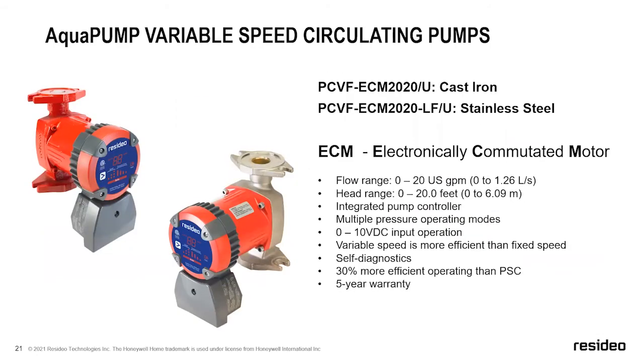And I did want to touch on our variable speed pumps. So we have finally entered the realm of variable speed pumps. We have had 3-speed fixed circulators for a while. We are now finally producing an ECM variable speed pump. So we are offering our same curve on our lower circulator, but we're offering it in 2 different configurations. So we got cast iron and stainless steel. And as I had mentioned previously, if you have any kind of oxygen issues on your system, you need to go to stainless steel. If you're doing hydro air that's open loop, you need to do stainless steel. So just something to keep in mind there.